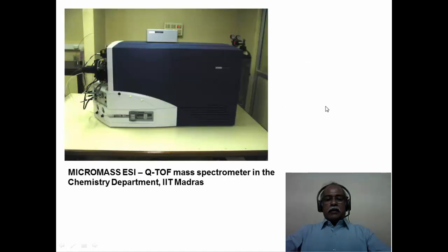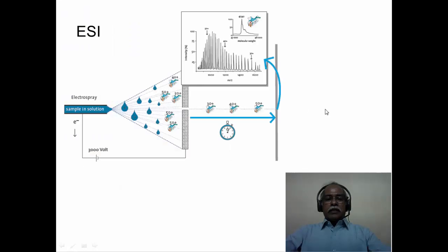Here is an electrospray ionization mass spectrometer housed in the Department of Chemistry at IIT Madras. You can see it is just a box that fits on a tabletop, but it can do wonders in terms of mass analysis, molecular weight determination, and sensitivity. In the electrospray ionization mass spectrometer, there is an injector which sprays the analyte solution as very fine droplets in a voltage region, where the sprayer is one electrode and there is a counter electrode. There is also a nebulizing gas passed through the sample.